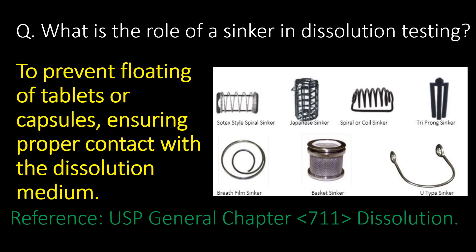What is the role of a sinker in dissolution testing? A sinker is used to prevent floating of tablets or capsules, ensuring proper contact with the dissolution medium. Reference: USP general chapter number 711, Dissolution.